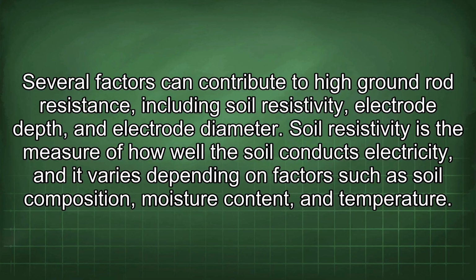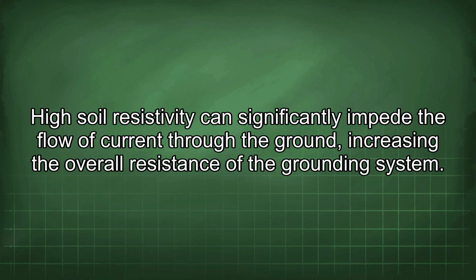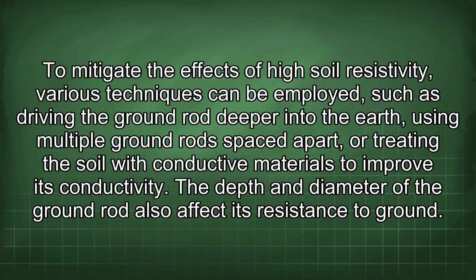Soil resistivity is the measure of how well the soil conducts electricity, and it varies depending on factors such as soil composition, moisture content, and temperature. High soil resistivity can significantly impede the flow of current through the ground, increasing the overall resistance of the grounding system. To mitigate the effects of high soil resistivity, various techniques can be employed, such as driving the ground rod deeper into the earth, using multiple ground rods spaced apart, or treating the soil with conductive materials to improve its conductivity.